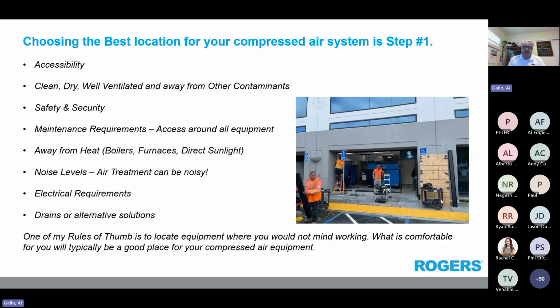Keep away from additional heat, boilers, furnaces, direct sunlight, and those kind of places. Those are not good for compressors. They're not good for air treatment, and so on and so forth. Noise levels. Air treatment makes noise. When those EDVs, electronic drain valves, go off, they can be startling. You don't want to set it next to an office where people are going to be working, or next to someplace on the assembly line that could be startling to people.